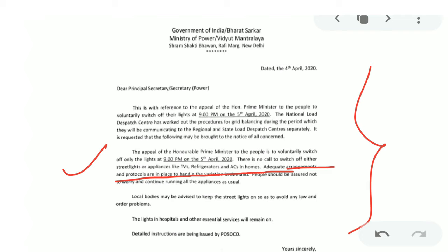This was said because if you shut down everything, there will be an unprecedented decline in the whole demand. And that amount of decline will result into failure of the coal-based thermal power plant and various other power plants, even if the whole event is known. Okay, so the request was made that you should only strictly turn off the lights that you have in your home, not street lights, no TV, no refrigerator, no AC should be turned off. There should be a minimum amount of load on the consumer end so that the whole system can remain in stability.